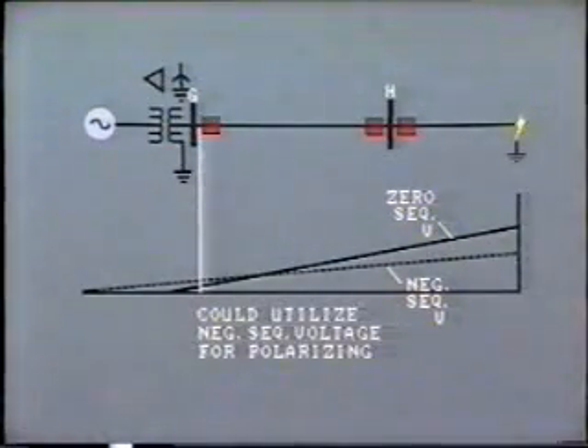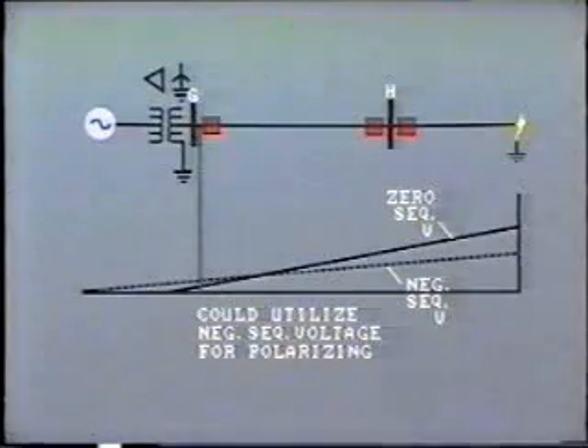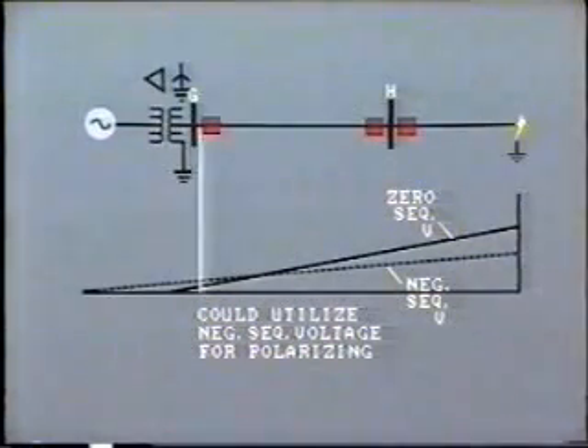One way around this problem is to utilize as a polarizing source the negative sequence voltage instead of the zero sequence. You'll remember that during a ground fault, negative sequence voltages are created. As shown on this curve, they are lower in magnitude at the fault and fall close to 0 at the source. However, at the location of the relay, the negative sequence voltage is generally, but not always, higher than the zero sequence voltage. This really depends upon the location of the relay and the characteristics of the circuit. A careful analysis would have to be made before applying this method.